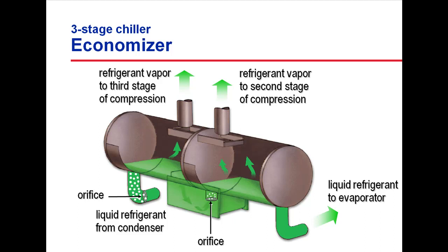The second expansion device further reduces the pressure of the refrigerant to that of the second stage impeller inlet. This pressure drop causes a portion of the liquid refrigerant to flash, and the resulting mixture of liquid and vapor enters the low-pressure chamber of the economizer.